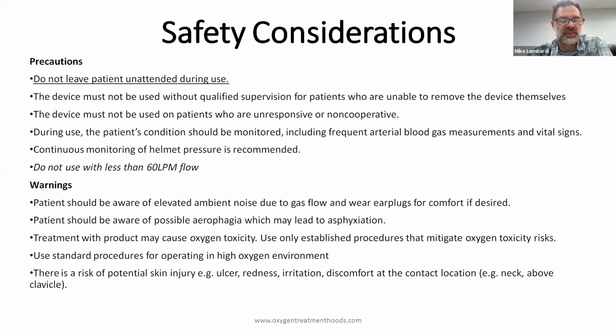And as I mentioned, we do not want to use the helmets with less than 60 liters per minute of flow. The patient should be aware of elevated noise. They should also be aware of aerophagia and those risks associated with swallowing air. And from a physician standpoint, we want to be aware of oxygen toxicity. Now, there's nothing out of the ordinary with using the hoods that would increase oxygen toxicity any more than with other modes of non-invasive ventilation. So you want to follow your standard guidelines for when the patient's exposed to higher than normal levels of oxygen.